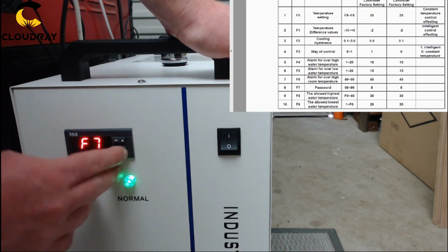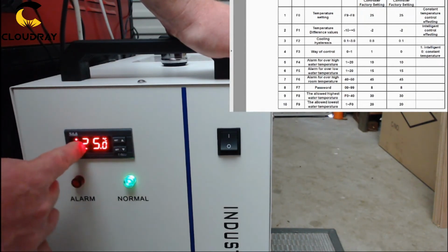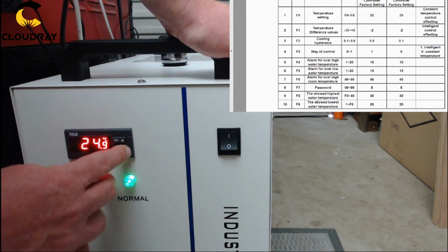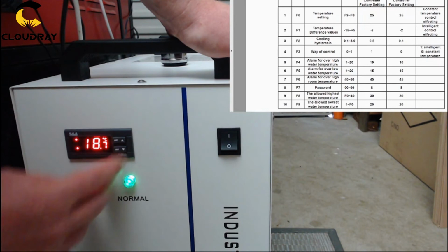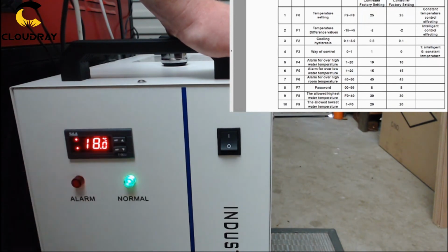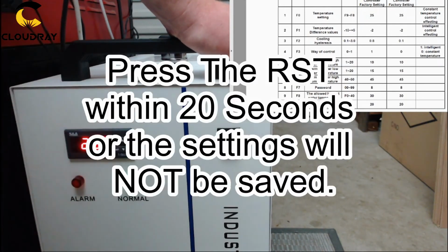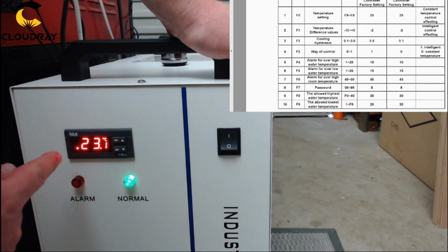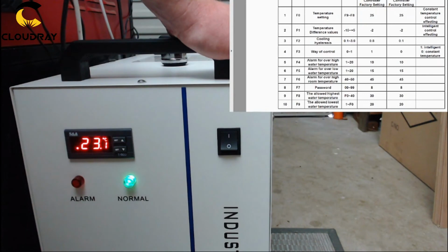Now we need to look at F0. We're going to change this temperature, which is our constant temperature that we require, to 18 degrees. And press set. And now to save, you need to press the RST button and everything will be saved. This will now drop the temperature to the 18 degrees and maintain it at a constant temperature.